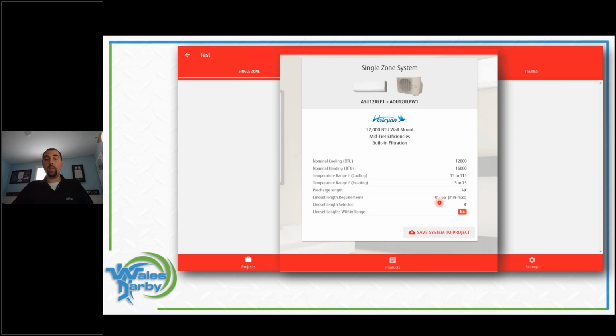Well, maybe there I'm on a service call and that's probably my issue. The customer's calling because they get a noise on the indoor unit every time this thing runs. That's the refrigerant rushing through the unit because the line sets are too short. Well, I can take this little app now, show my homeowner, look, we didn't install this, but this is your problem. Your line sets are too short. I got to move your outdoor unit 4 feet over. I got to find a way to coil up maybe horizontally a line set, get it out of the way so we can make up that additional length.